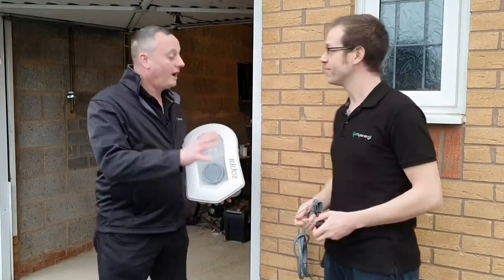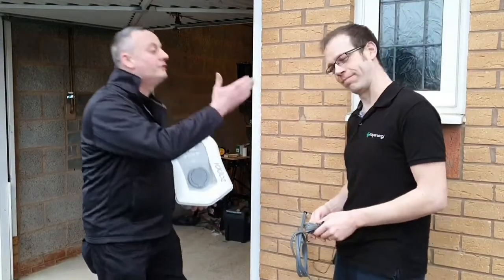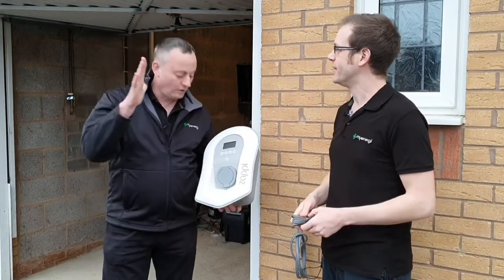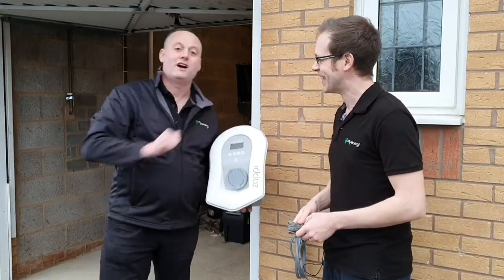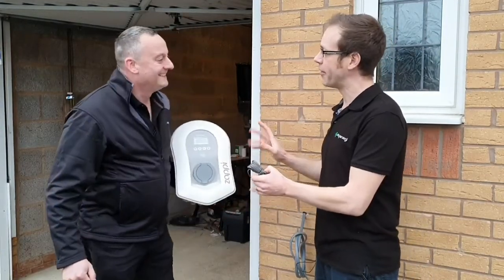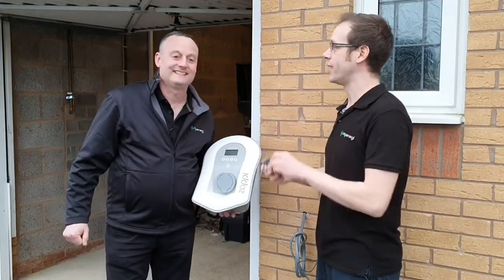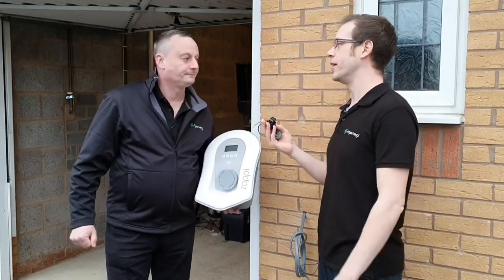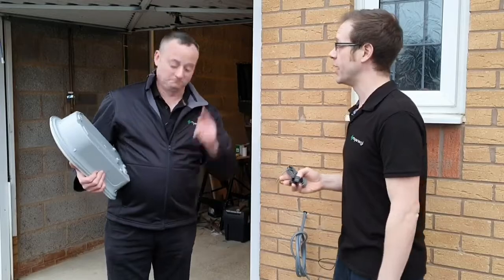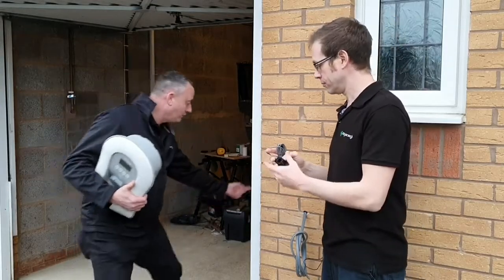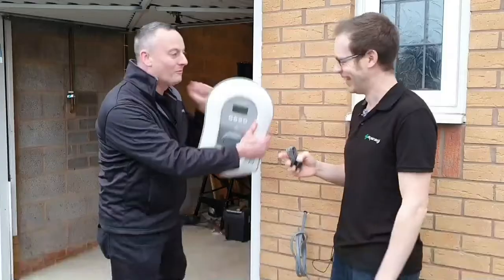So we've wired our circuit, Joe, the 6mm squared cables here, our consumer unit's installed, we're ready to install our Zappi 2 EV charging point. I know you're really excited about installing that, Gary, but before we do that, we've got to get the CT installed. We've got to get this wired in. So I think we need to just hold off doing that a second. I think if we take this end here and I just poke it through here, Joe, we're off and fitting.